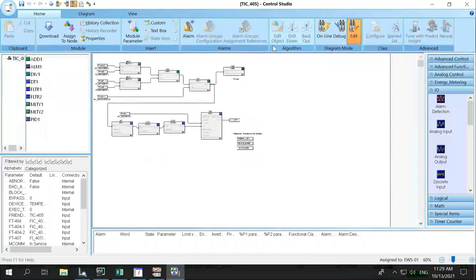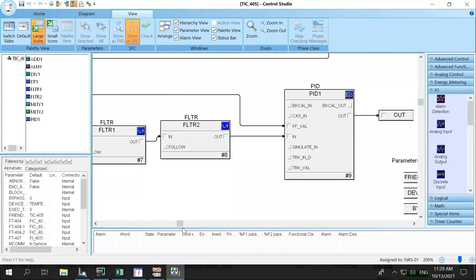There's the PID block right here, and this is the input. I built in two time constants to be able to simulate my temperature, and there's my feed forward value right here. The feed forward value comes from the flow, and that flow coming in is the actual configuration for the feed forward block.